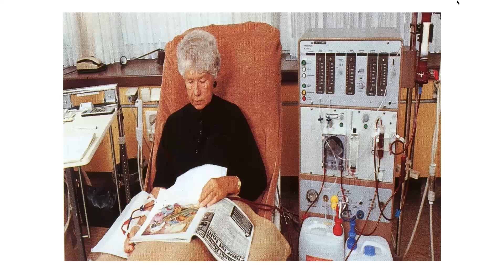So what ended up was a concentrate that was said to be normal, but was no longer a normal concentrate, because the issue that gave you that conductivity alarm was never corrected. Did they correct the settings in these machines? No. So it alarmed again, and you changed it again. That's when the requirement came that you must match your reading to a handheld to make sure those manipulations did not occur. And this has existed since the late 1970s.